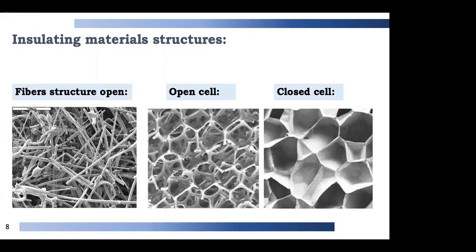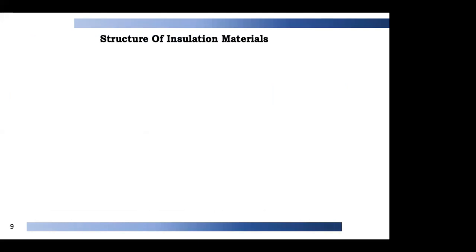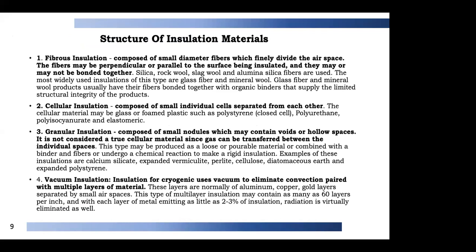Insulation material structures are bifurcated into three major parts: one is fiber structures, which are open fiber structures; second is open cell insulation; and third is closed cell insulation. Fibrous insulation is composed of small diameter fibers which finely divide the air space — examples include rock wool and mineral wool. Cellular insulation covers closed cell insulation such as nitrile rubber, XLP and EPDM. Granular insulation is composed of small nodules which may contain voids or hollow spaces — examples include calcium silicate, expanded vermiculite or perlite and cellulose. Vacuum insulation is applied for very high or low temperatures with layers of aluminum, copper or gold.